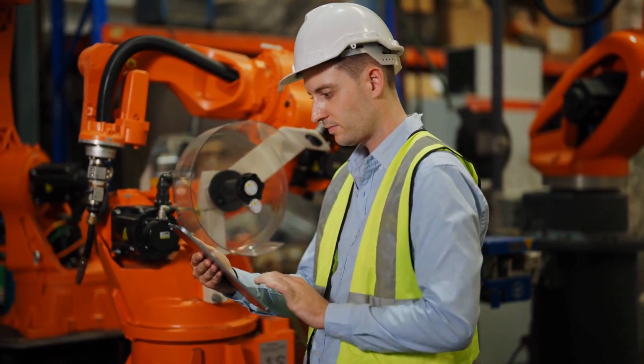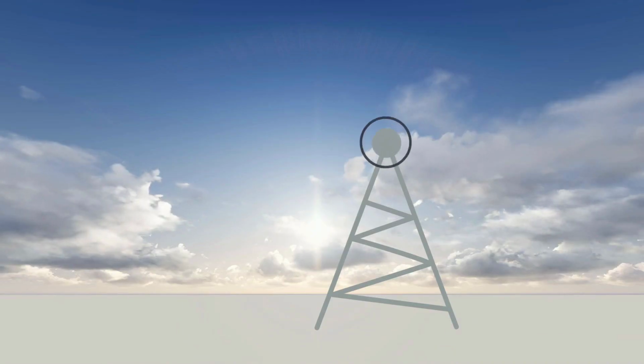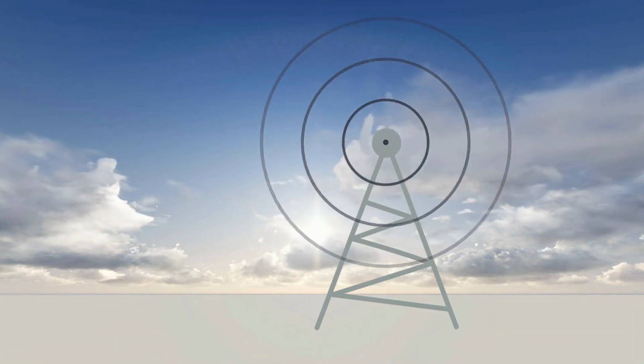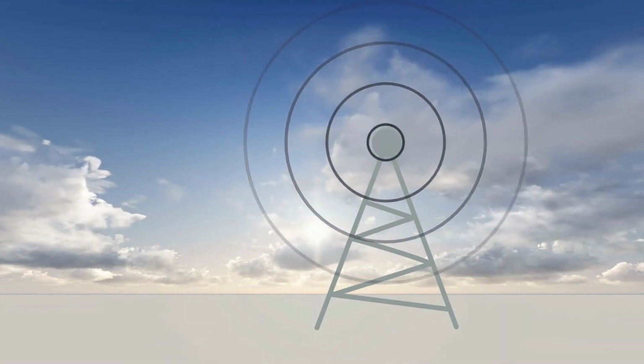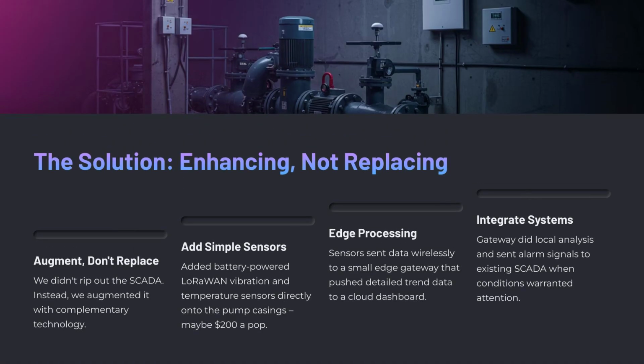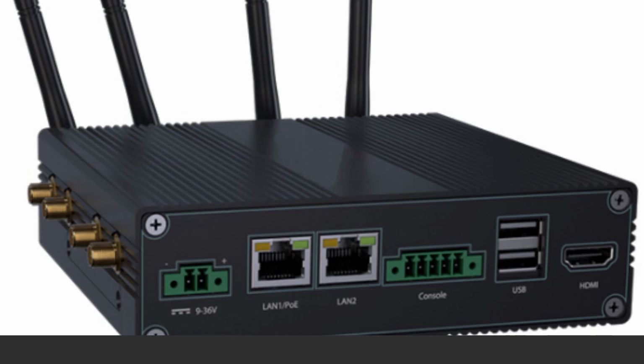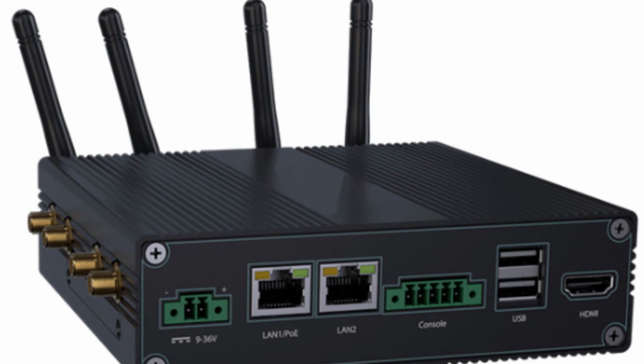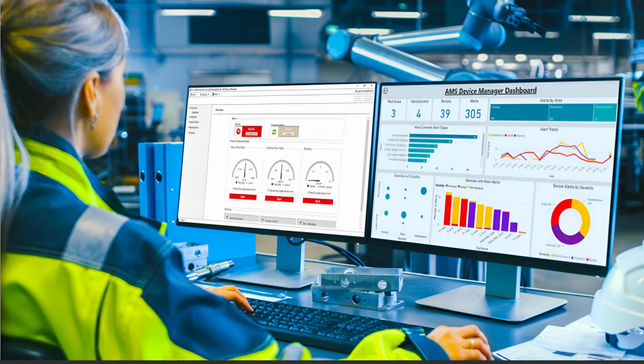We didn't rip out the SCADA. Instead, we augmented it. We added simple, battery-powered, long-range, wide-area network vibration and temperature sensors directly onto the pump casings, maybe $200 a pop. These sensors sent their data wirelessly to a small edge gateway installed at the station. That gateway did two things. First, it pushed the detailed trend data, vibration spectrum, temperature history, up via cellular to a cloud dashboard. Maintenance could now see detailed health information from anywhere. Second, the gateway did some local analysis.